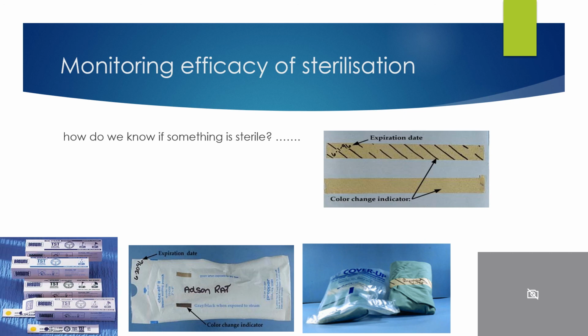and some practices, depending on the sorts of instruments, gowns and equipment that they are sterilising, may also use Bowie-Dick tests, which can be seen bottom right and also top right. However, that only changes at 121 degrees C, and we generally would be looking for a higher temperature than that, and this is where our TST strips come in.